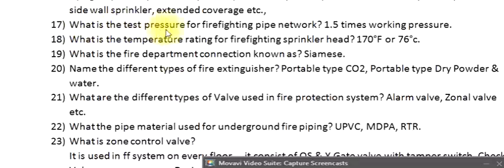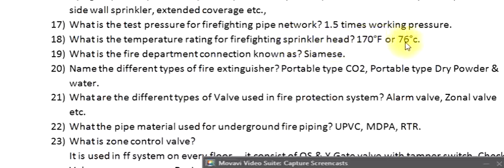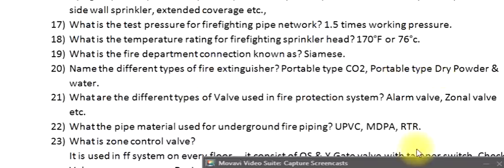Question 17: What is the test pressure for a firefighting pipe network? 1.5 times working pressure. Question 18: What is the temperature rating for a firefighting sprinkler head? 170°F or 76°C. Question 19: What is the fire department connection known as? Siamese. Question 20: Name the different types of fire extinguisher. Portable type CO2, portable type dry powder, water.